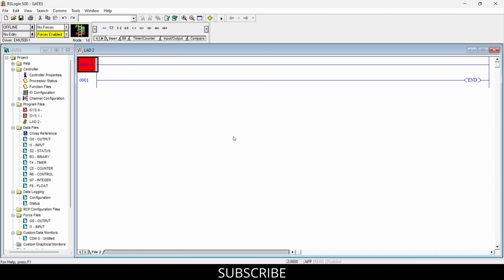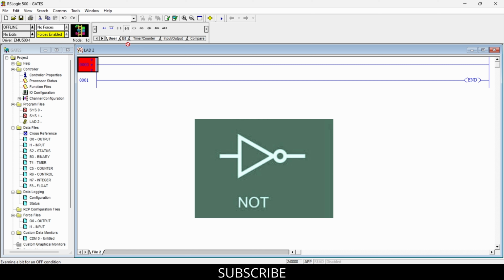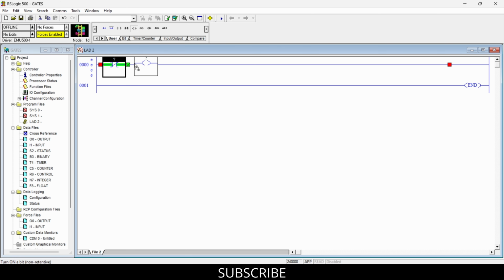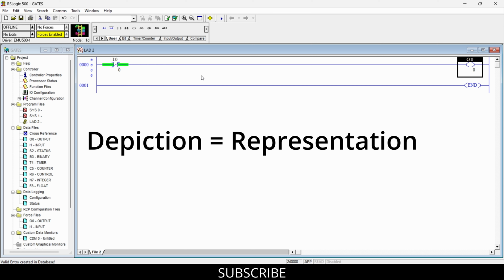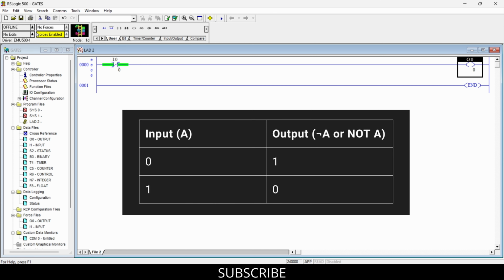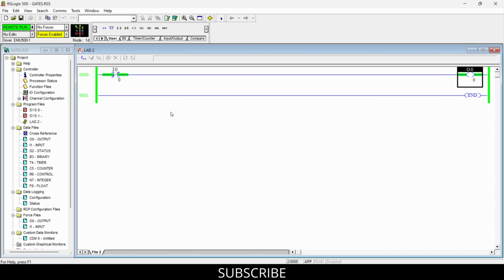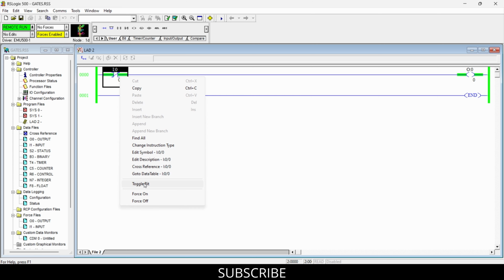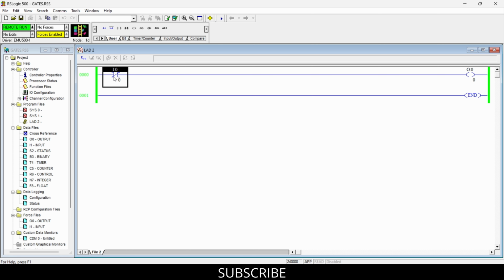So let's start with our first logic gate, which is NOT gate. For NOT gate, we need one NC contact and one output coil. So here you can see the ladder depiction of NOT gate, and the truth table of NOT gate is this. So let's check how NOT gate works. The basic concept of NOT gate is the inversion concept, because if you toggle your input, the output will go off, and if you untoggle the bit, the output will go on.